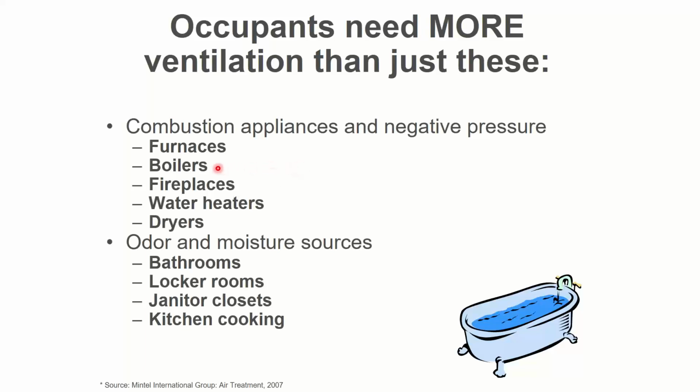If you need to bring 500 CFM in for some big giant boiler, that's fine. You have to do that. It doesn't count towards your ventilation requirements that I'm about to explain.